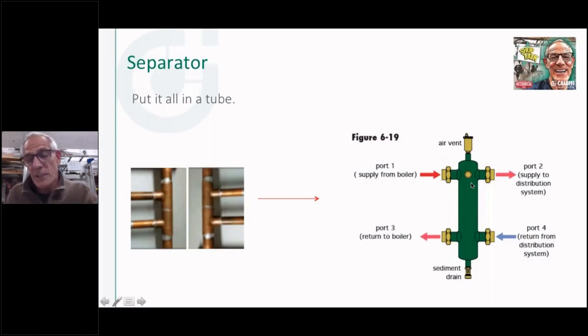So getting back to this, so we said, okay, I think we're onto something here. We've got a better mousetrap. We can make it simpler for the installer. He doesn't have to assemble this on the job. If this is sized properly, it's going to work. There's nothing you could do with the pumping on either side of this, if this is sized properly for the flow rate, and we'll get to that in a minute, that you won't have hydraulic separation.